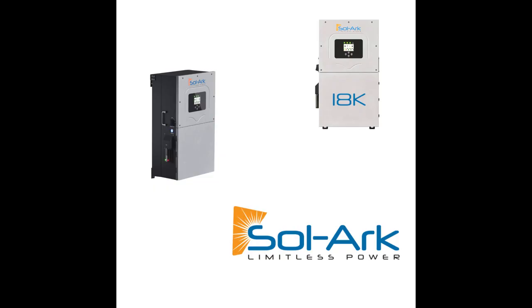Next thing, which we're still kind of, I don't have the exact value, unfortunately, but the 12-volt power supply that we have on board our system, specifically for the rapid shutdown. So the issue that we've had in the past, right, with the 15K and 12K is that most RSD transmitters pull more than 100 milliamps. So the solution has been pulling power off the load output of the inverter to be able to power that transmitter. Sometimes it's a pain to have to run AC power just to run the transmitter. So we've solved that issue with the 18K. So you do have the ability to pull DC power directly off of the inverter to power that transmitter.